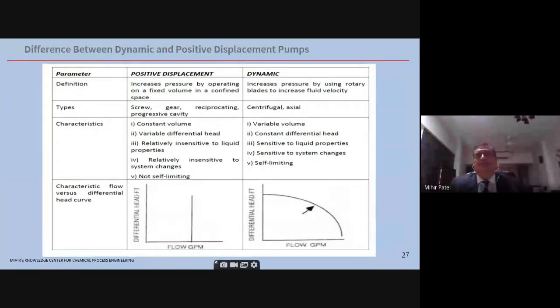So with more back pressure, the pump will keep on building pressure until either the casing breaks or the safety valve on the discharge side activates. Whereas a dynamic pump, which is a centrifugal pump, has a different principle. It increases pressure by using rotary plates to increase fluid velocity, which converts into pressure head in the casing.